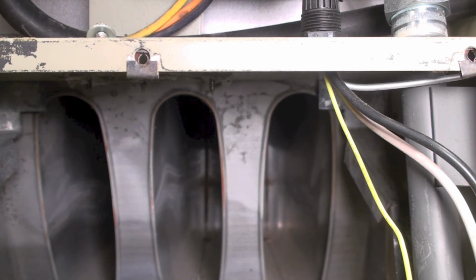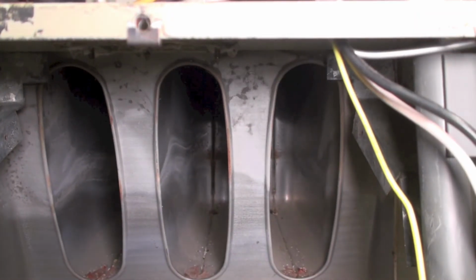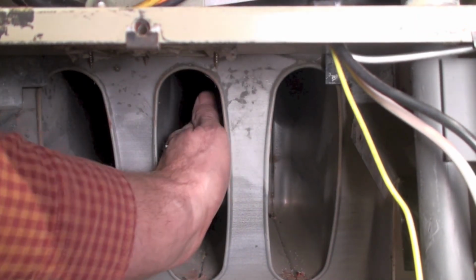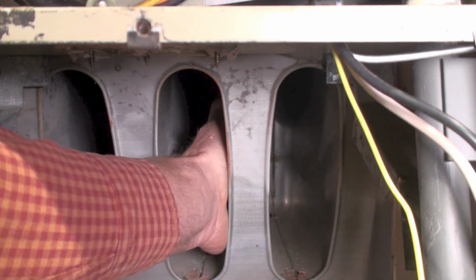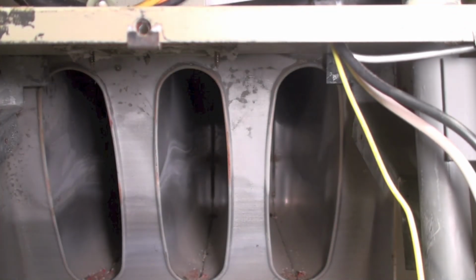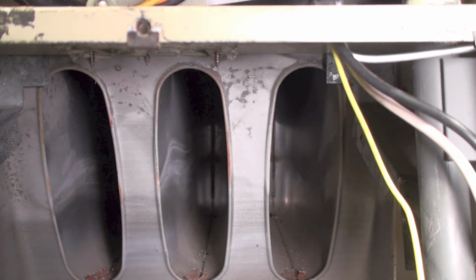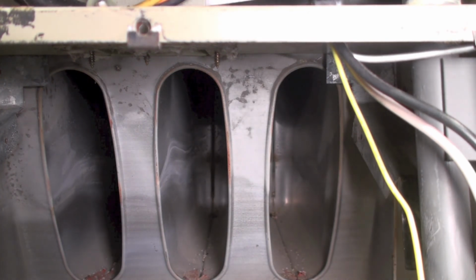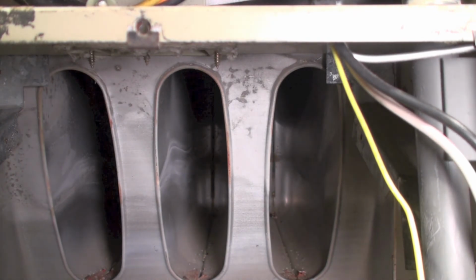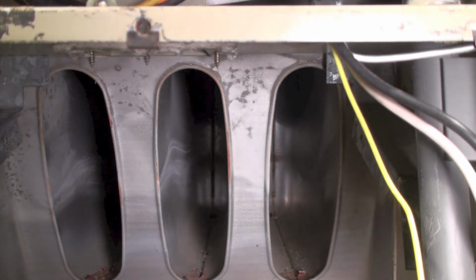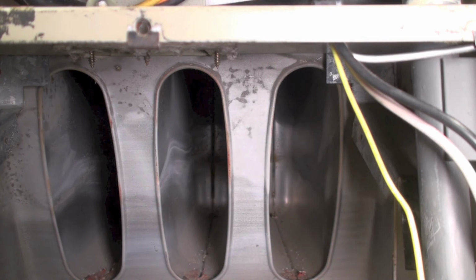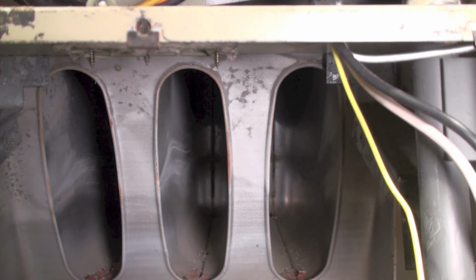Okay, you got a mandatory heat exchanger check with all these, and I've got the burners out of this thing now. You can see the burners are gone. And looking up in here, using your hands wherever you can, get a flashlight in there, something like that, and check out those heat exchanger tubes. If it's really dirty in there, vacuum it out. But it is a mandatory heat exchanger check on these things every time. Be very thorough with these heat exchanger checks.